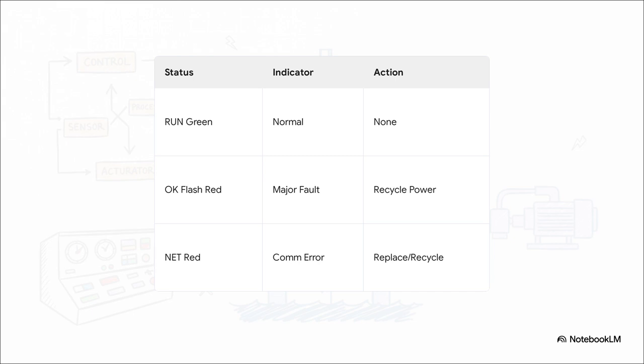But a flashing red light on your PLC, that indicates a major recoverable fault. And a solid red net fault on your Ethernet modules means a severe communication error, like a severed cable or a duplicate IP address on the network. When you see red, it demands immediate troubleshooting.